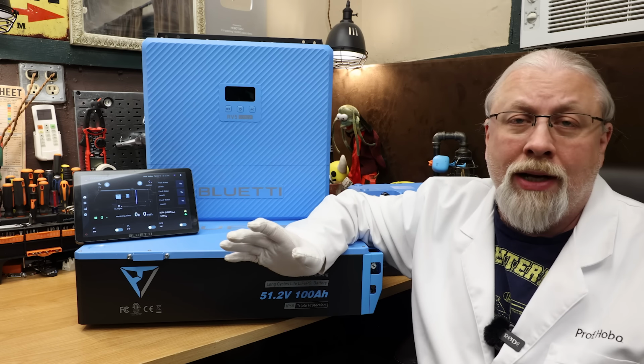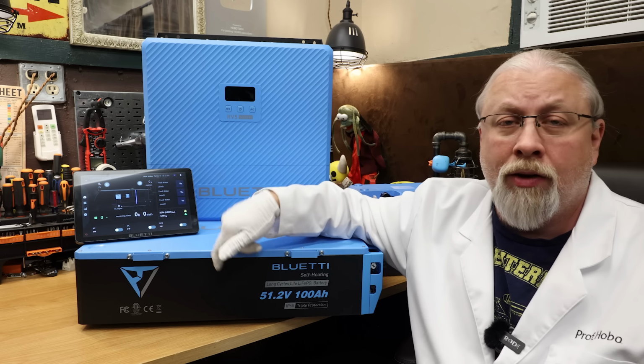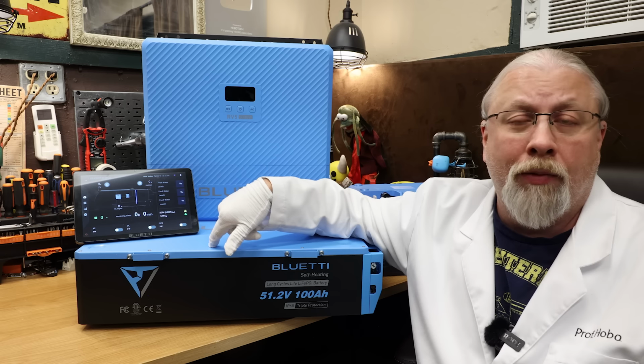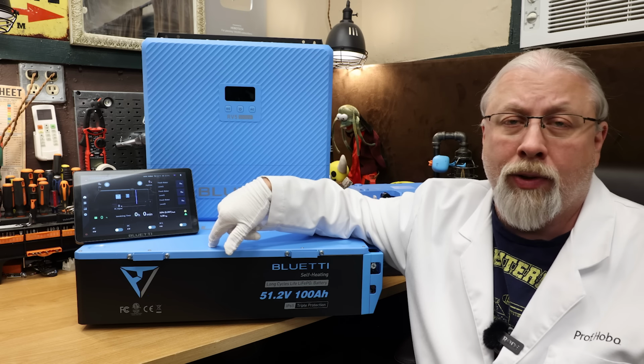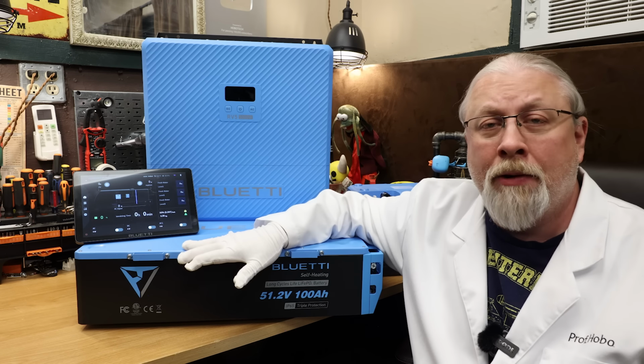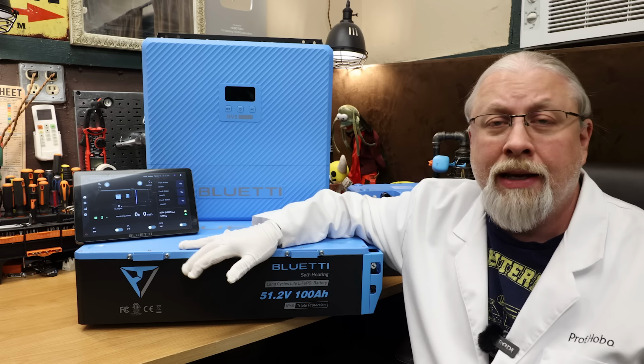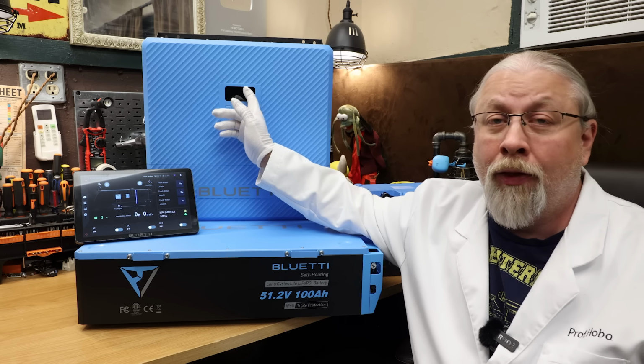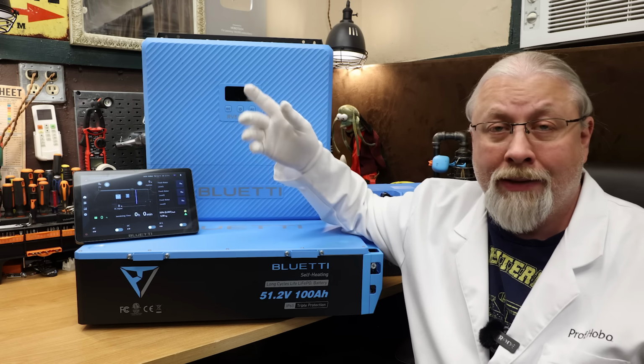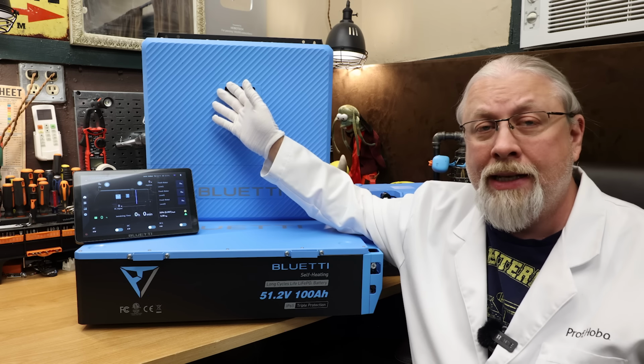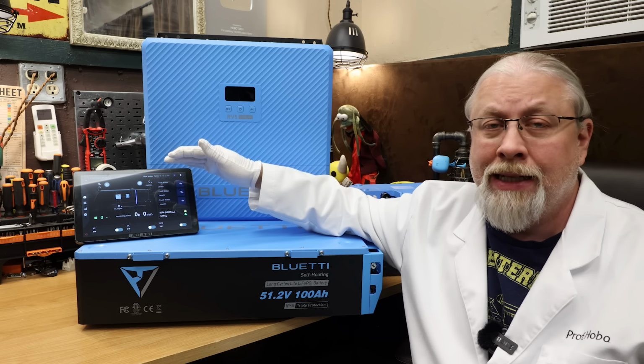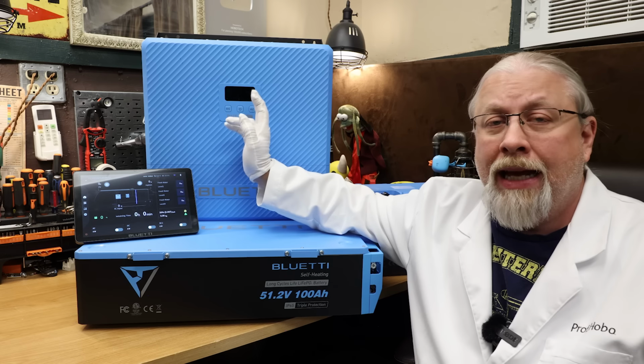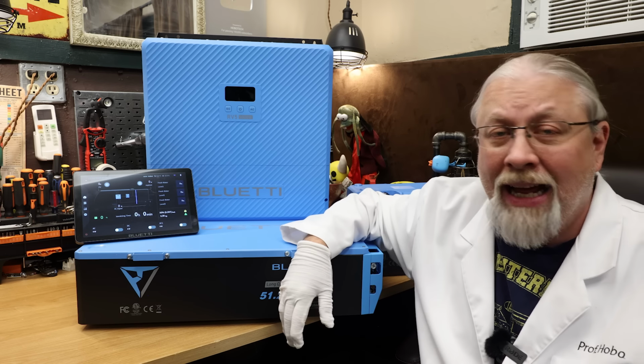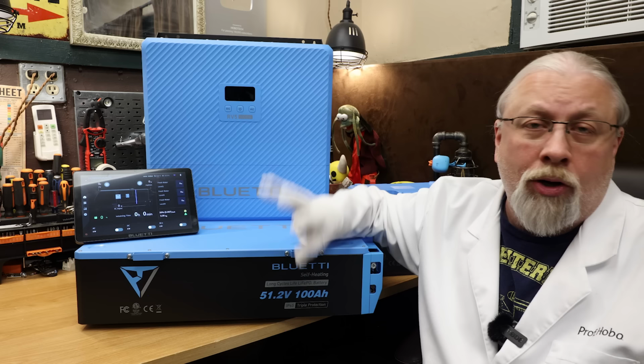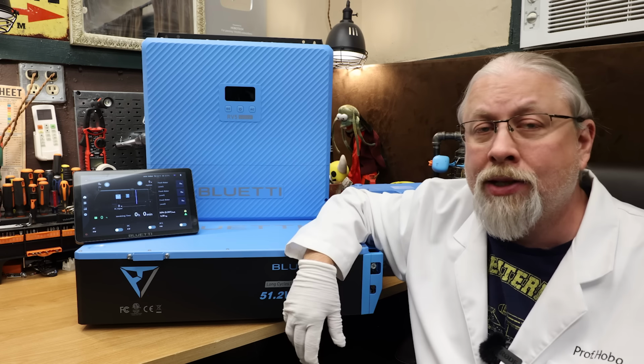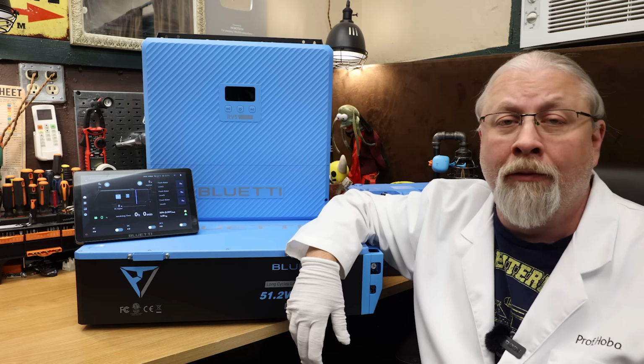Let's rate the idle run times for these scenarios, assuming a single B4810 battery has 4.6 kilowatt hours of usable capacity. The unit just powered on with nothing else would run the RV5 for about 32 days before dying, and that's excellent. If we add in just the DC side, that drops the runtime down to 19 days. If we had both AC and DC, it'll run about 8.5 days. At max, with the whole shebang including the ePad screen, it will live for about a week before dying.